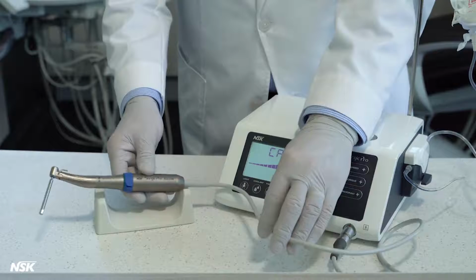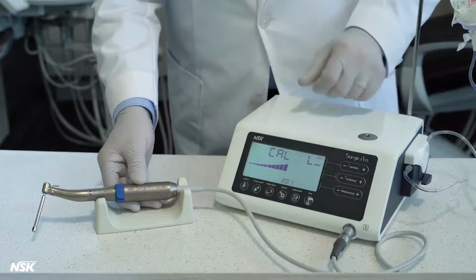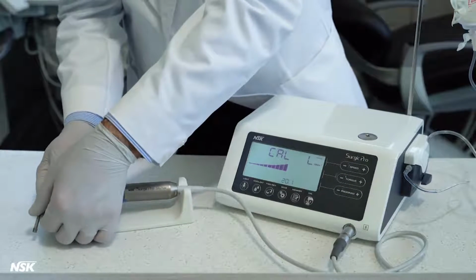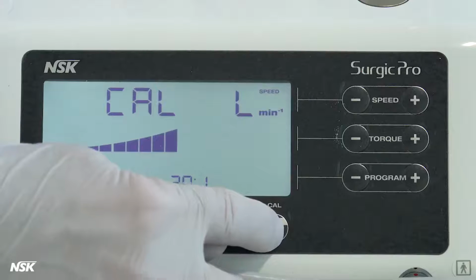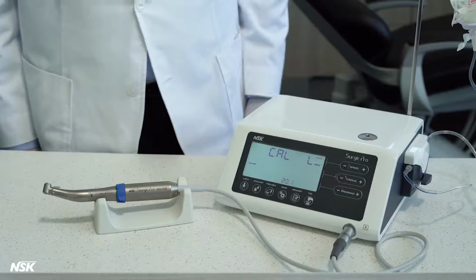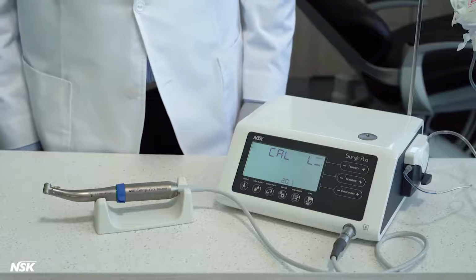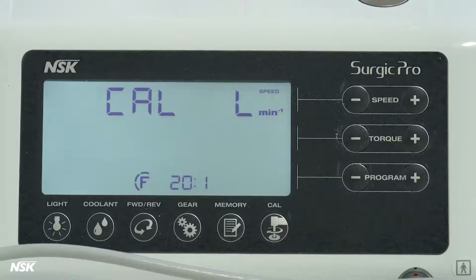Step 3. Speed calibration. Remove the drill and leave the motor and the attachment on the handpiece stand. Press the Cal key. The attachment will start working and rotate for 8 seconds at slow speed and another 8 seconds at fast speed. When it's done, you will hear a beep and the calibration process is complete.